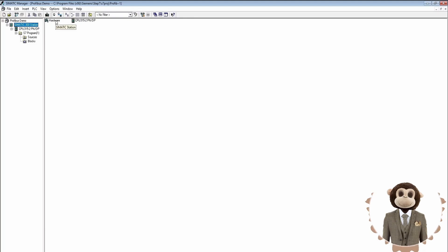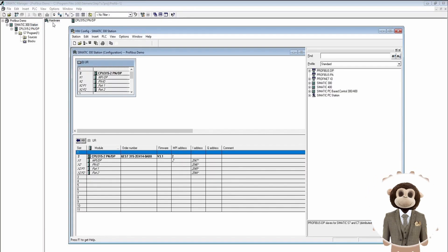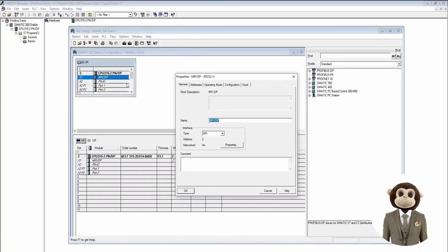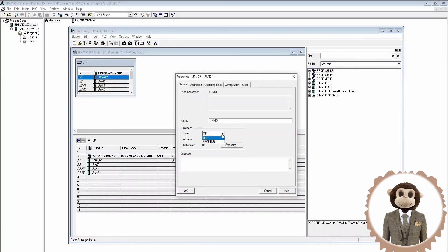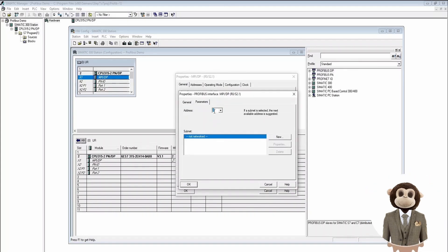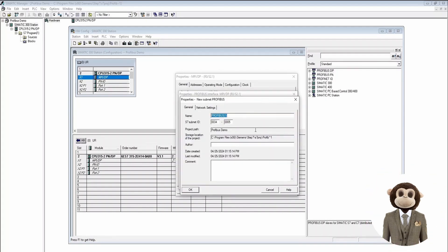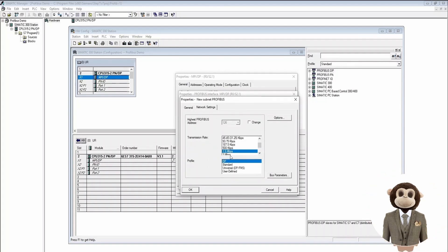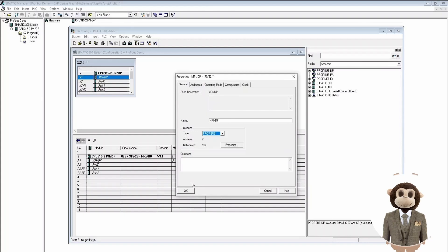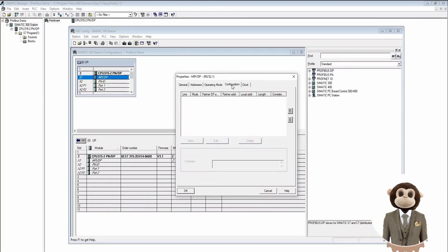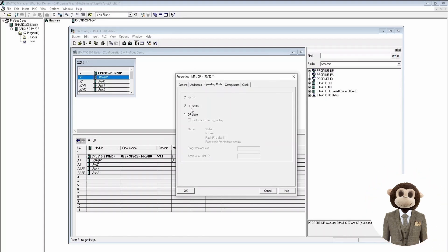Now we need to set up the hardware configuration. We go to the SIMATIC station and double-click Hardware. We need to set up the PROFIBUS interface, so we double-click on MPI/DP and change the interface type to PROFIBUS. This is the node address of the PLC — we'll leave that as default — and then we add the network, leaving the name and transmission rate as default, and verify that the profile is set as DP. We accept that and verify in operating mode that we are set up as a DP master.